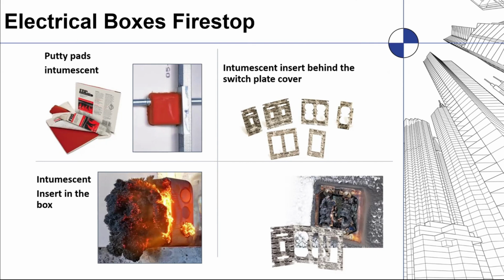But if you're at a later stage of construction and didn't get the electrical box covered with putty before the gypsum was in place, you can still fire rate the box from inside the face of the box by putting a box guard inside. And if the gypsum and electrical wiring are already in place, you can put a box guard called a cover guard underneath the cover plate, which seals it off and creates the same fire-rated standard for the electrical box.